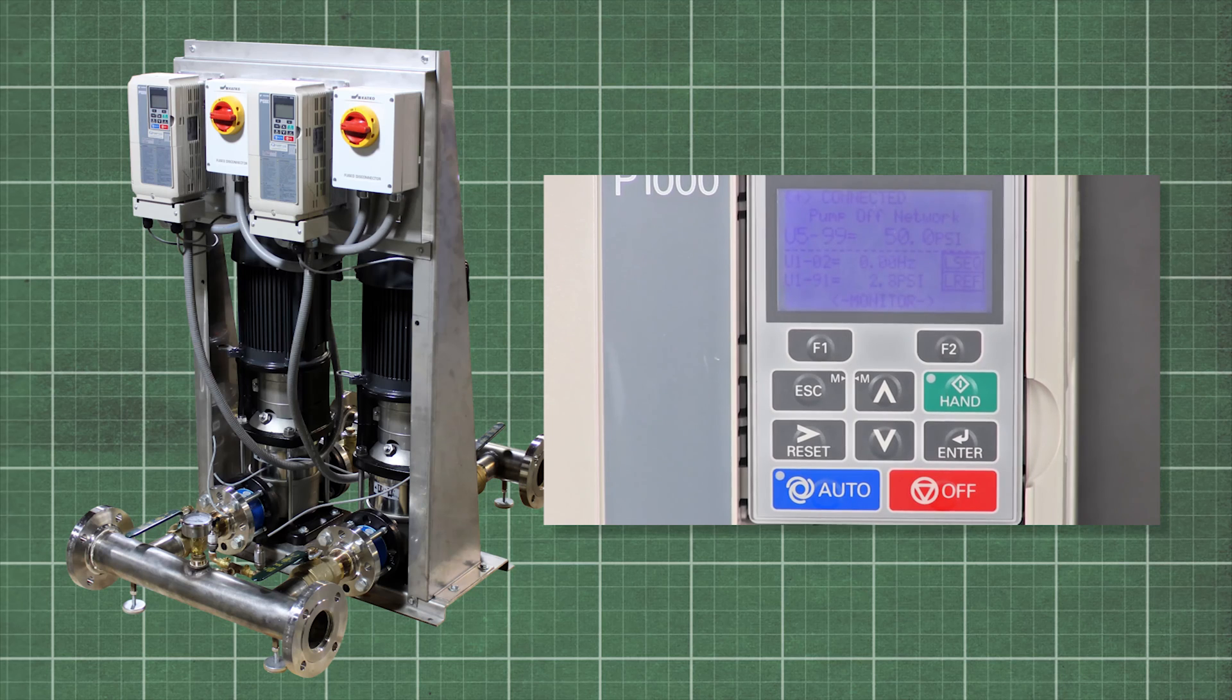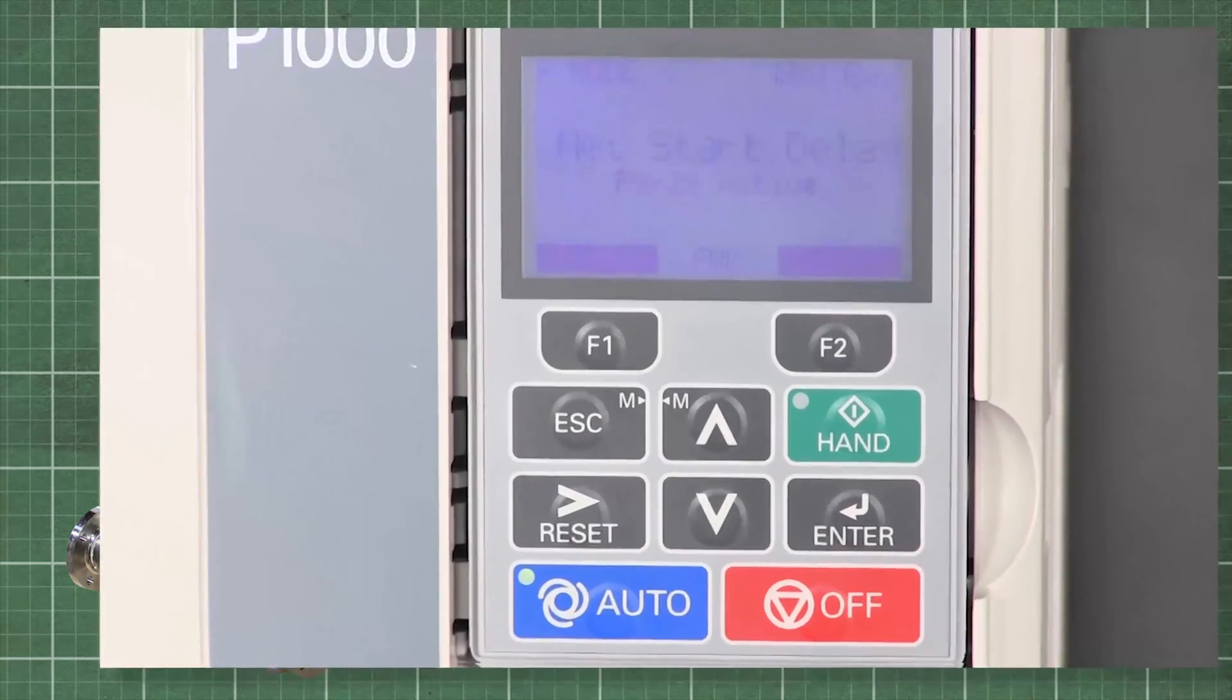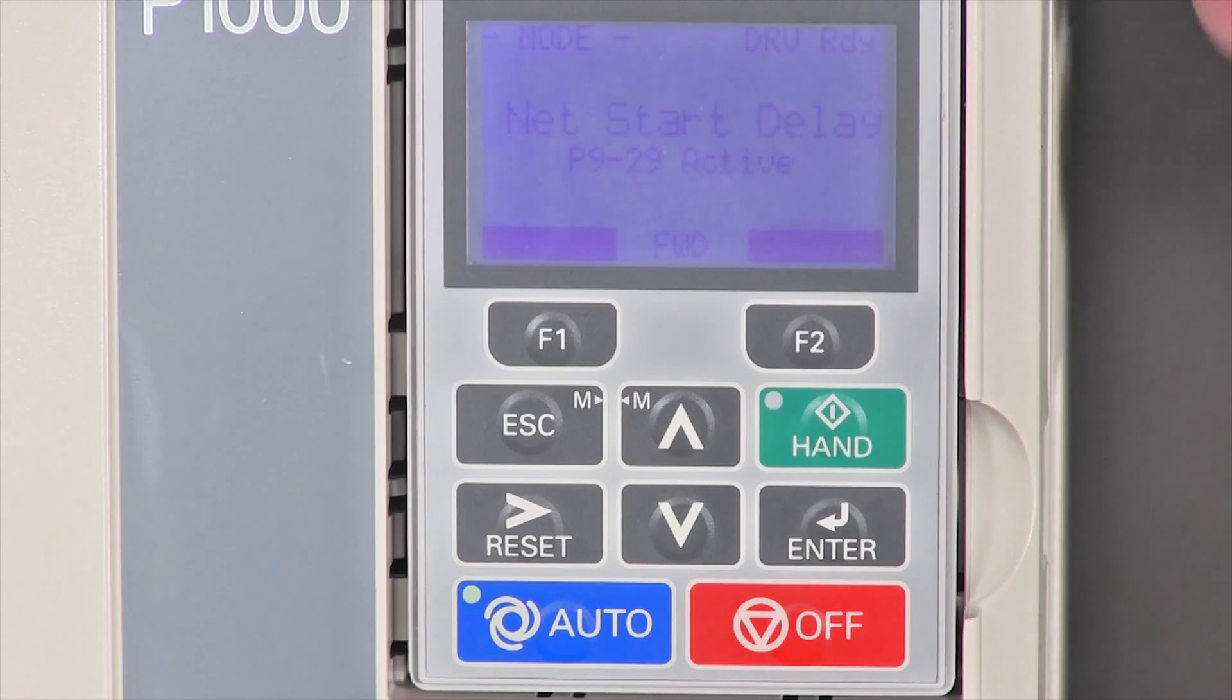Now we're ready to run in auto mode. The drive has been programmed for a set point of 50 PSI. Press the auto button. The pump should speed up and pressurize the system to 50 PSI. Check for leaks and close any open faucets or hoses.